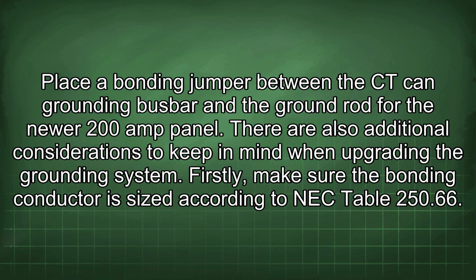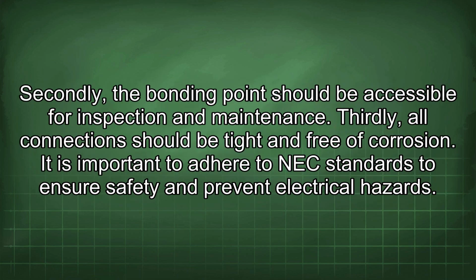There are also additional considerations to keep in mind when upgrading the grounding system. Firstly, make sure the bonding conductor is sized according to NEC Table 250.66. Secondly, the bonding point should be accessible for inspection and maintenance. Thirdly, all connections should be tight and free of corrosion. It is important to adhere to NEC standards to ensure safety and prevent electrical hazards.